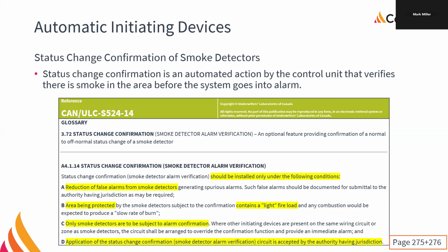Because the smoke detector latches, we reset the power, so it's unlatched, and if it goes back into alarm, then it's going to set off the bells. It's going to call the fire department, all that stuff. So we've added a 30-second delay in activating the fire alarm system. Okay, yes, it's going to reduce false alarms, but that's an additional 30 seconds before the bells go off, before the signal even gets to the fire department. So it's going to be a slower response time.